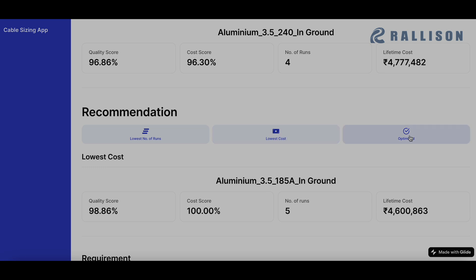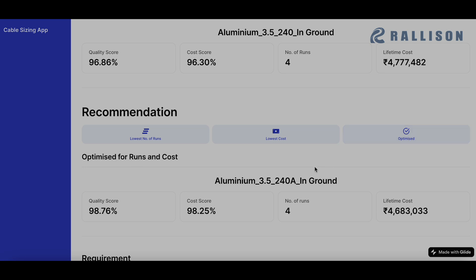We can also go in for the optimized solution. This takes into account both the lowest number of runs and the lowest cost. And in this case, we see a 240 square mm enhanced cable is what it recommends because it increases the quality score at the same time reducing the cost.